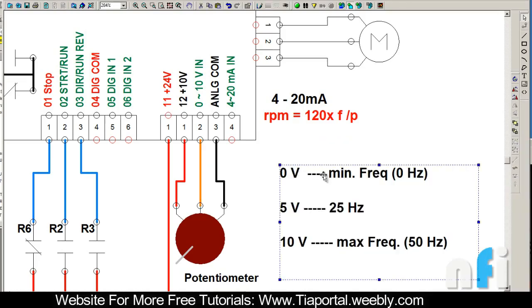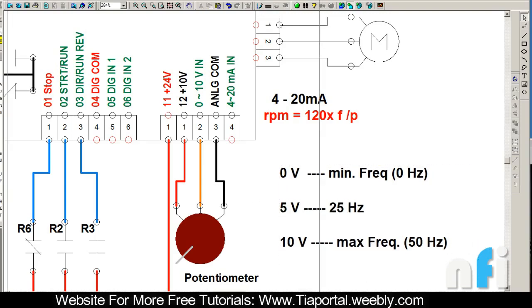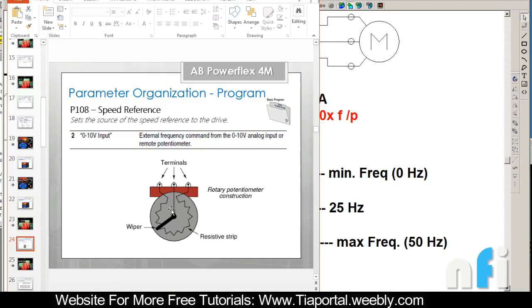When you have zero volt, the drive will run at minimum frequency, zero hertz. When the potentiometer is giving 10 volt, it will run the drive at maximum frequency, and in between 5 volt it has 25 hertz. So you'll find that at 1 volt of jump you have 5 hertz of increase, because at 10 volt it's 50 hertz. At 1 volt it will be 50 divided by 10, which is 5 hertz.